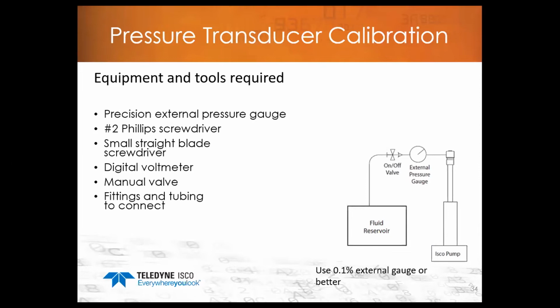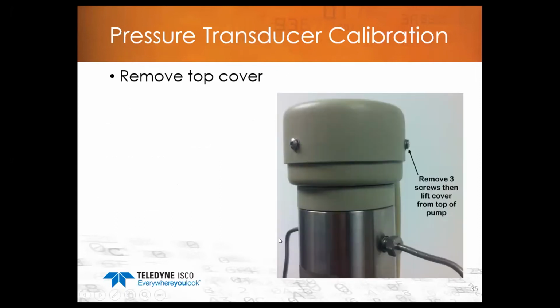And there's a diagram there that shows a setup of a pump with an external pressure gauge connected to it, an on-off valve, and then a reservoir to fill the pump with water. You'll need to remove the top cover on your pressure transducer. There are 3 screws that remove that top round cover, and that will then give you access to the pressure transducer circuit board that's located on top of the pressure transducer.